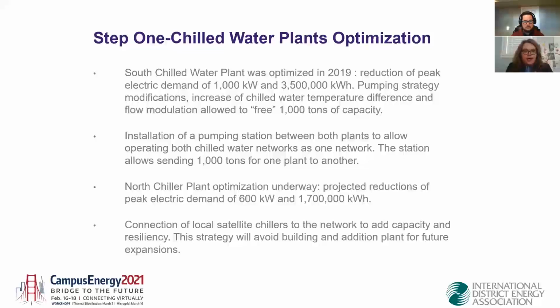low delta T syndrome that was experienced on the campus. To alleviate this, a project was done to have variable flow pumping, and projects were done in buildings to increase the delta T in the buildings. So that generated a reduction of about 1,000 kilowatts in demand and 3.5 million kilowatt hours in savings with that pumping strategy modification.